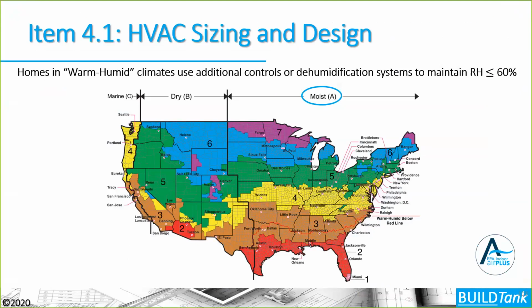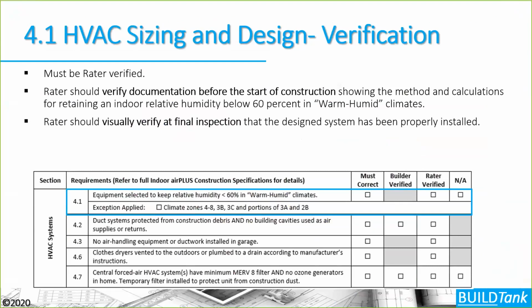So going through those 3 steps of getting our loads, choosing our equipment properly and then designing distribution systems makes sense regardless of the type of HVAC system you're going to install in that house. Now, these systems can be verified. Mainly, it's verified by the rater here. So you can see that although some items can be verified by the builder, in this section, you'll see the builder section there is grayed out, so the builder can't verify this. You're verifying documentation through the Energy Star program if you're using the rater verification reports or visually verifying these systems.